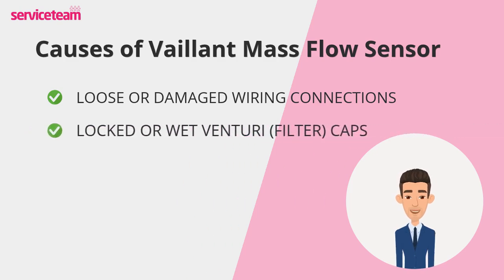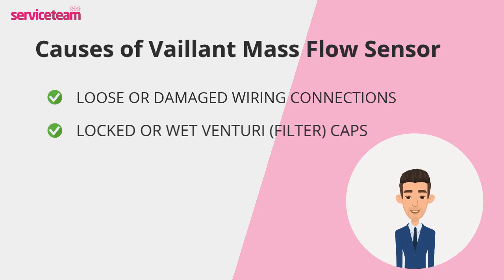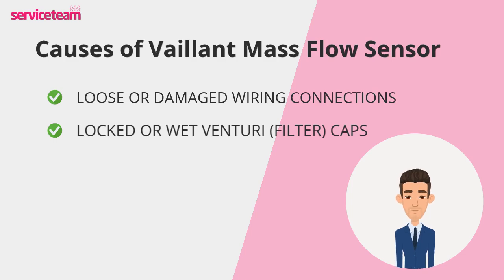The next cause is blocked or wet filter caps. The venturi filter cap regulates airflow to the sensor. Dirt, debris, or moisture can block the airflow, leading to incorrect sensor readings. This type of blockage usually causes an F53 error code — a sensor functionality problem — and can affect combustion efficiency.